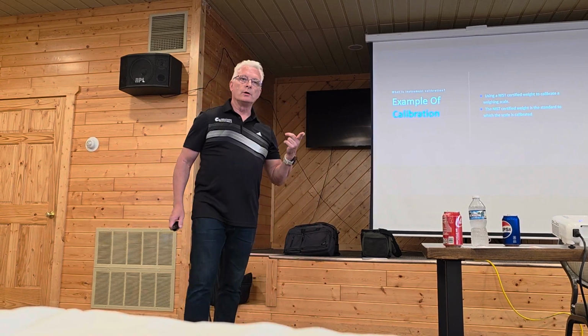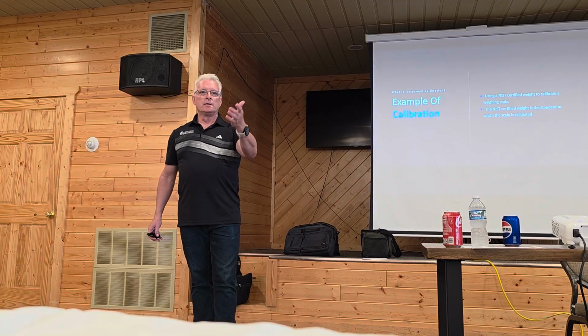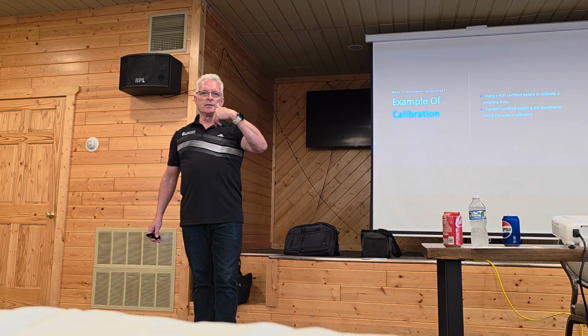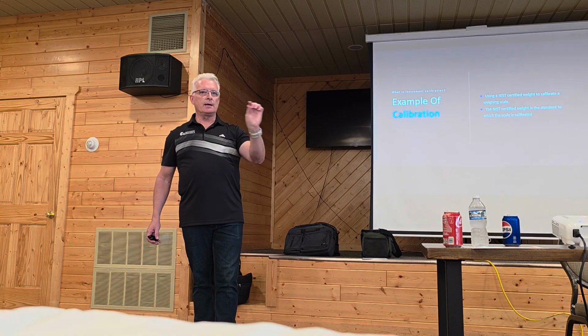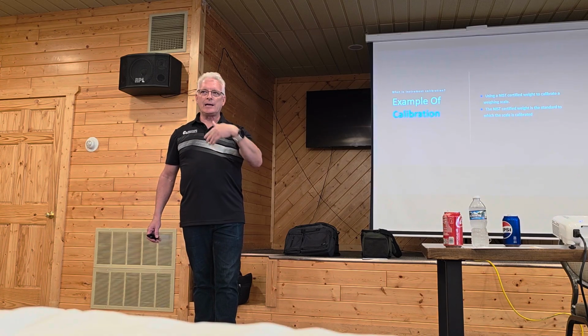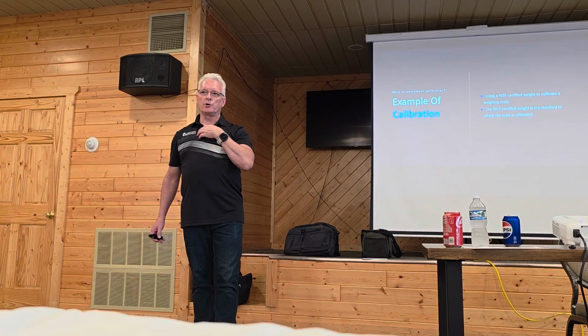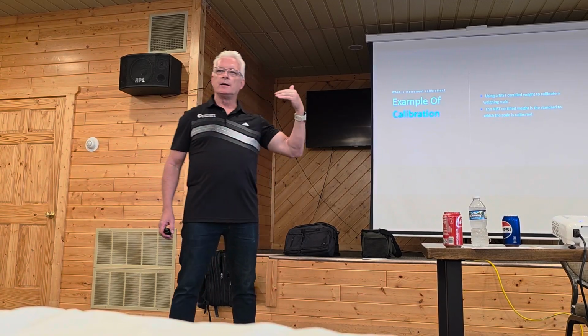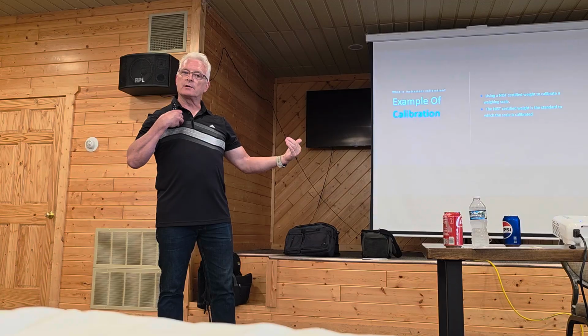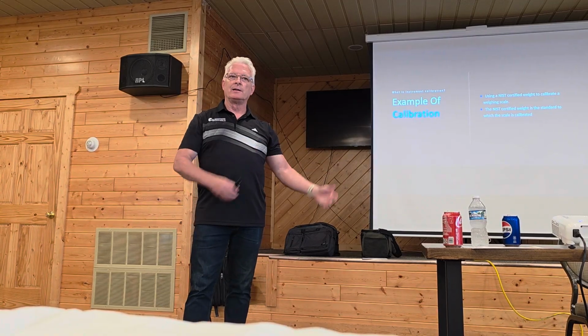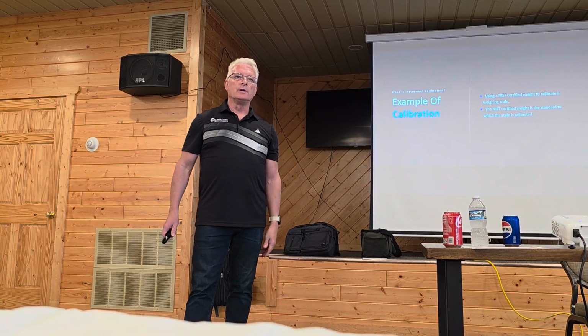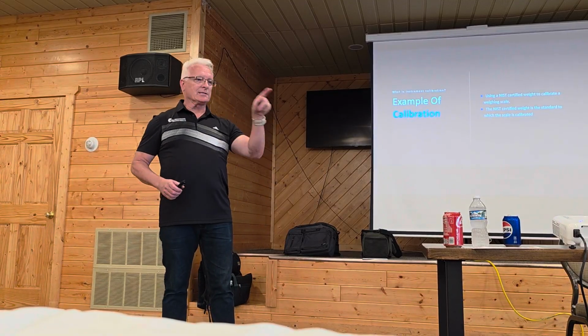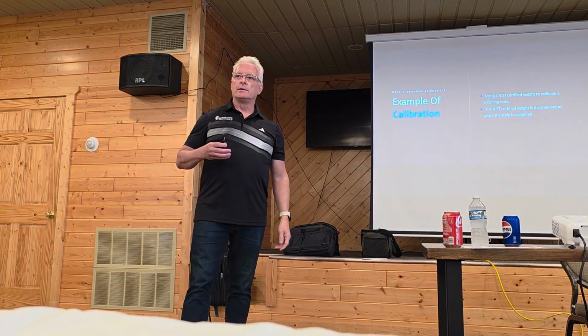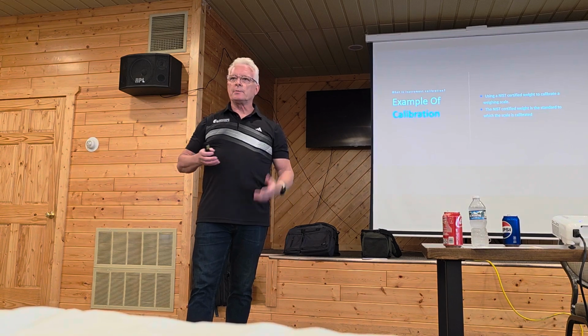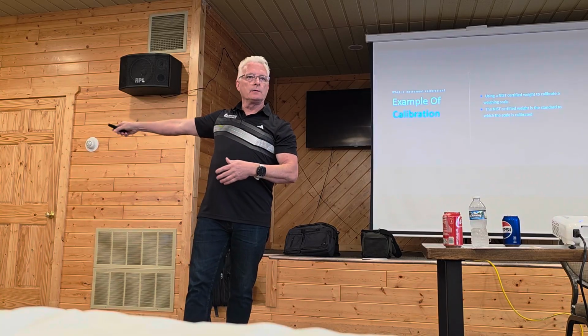And then on that report, like if we're doing a LEL gas, we bought standard gas reference, and on it tells a date and NIST and what lot it came from and everything. So now we are assured that that is as good as it can be, and that's what we test your equipment with, our equipment that's also been tested by NIST, so we can make sure it's as accurate as possible. And on the report, it will put that gas lot number and everything, so that when we go back, if somebody says, hey, this thing blew up, we can say, this is what we did, this is what we did it with, and it came from this lot.